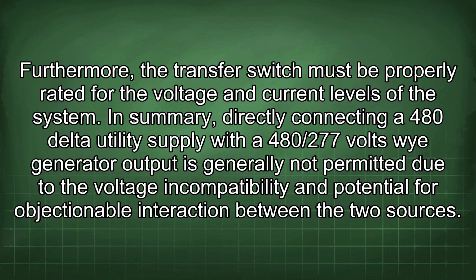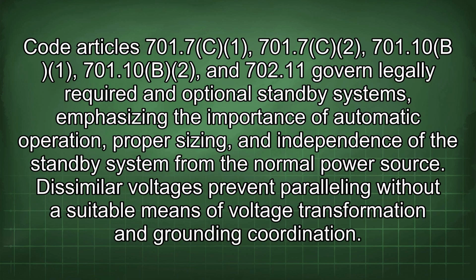In summary, directly connecting a 480 delta utility supply with a 480/277 volts wye generator output is generally not permitted due to the voltage incompatibility and potential for objectionable interaction between the two sources. Code Articles 701.7(C)(1), 701.7(C)(2), 701.10(B)(1), 701.10(B)(2), and 702.11 govern legally required and optional standby systems, emphasizing the importance of automatic operation, proper sizing, and independence of the standby system from the normal power source. Dissimilar voltages prevent paralleling without a suitable means of voltage transformation and grounding coordination.